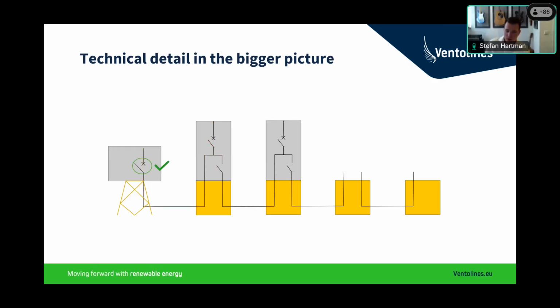We interrupt the trial run. Now the string can be de-energized from the offshore high voltage substation. That's what we see here, opening the circuit breaker. Now there's no more voltage on the cable. So next slide. We can move back to the turbine. On the first turbine, we close the disconnector and connect the outgoing cable. Now everything is connected.